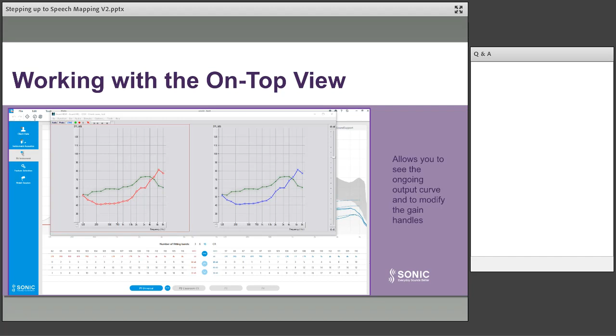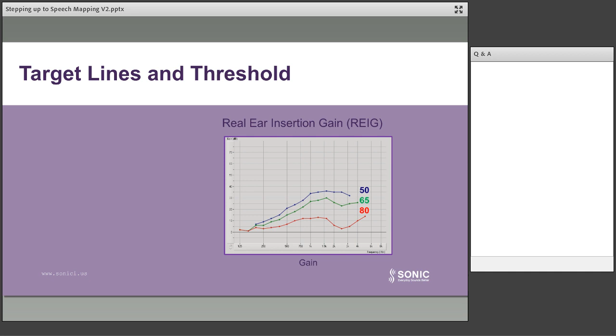Now, if you're doing insertion gain, then of course you're very used to these lines. So you've got the 50, 65 and 80. And we know that with wide dynamic range compression, as you increase the input level, you decrease the gain. So when you put a 50 dB stimulus in, you'll get a certain amount of gain. Then when you turn up the stimulus, you get less gain. And when you turn it up yet again to 80, you'll get less gain again.